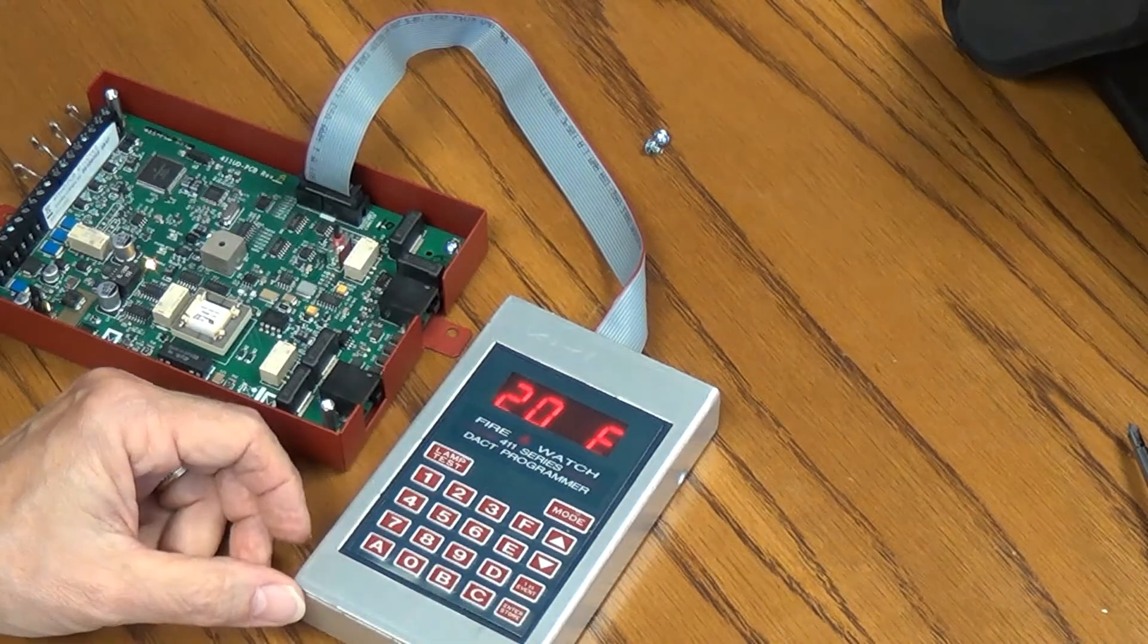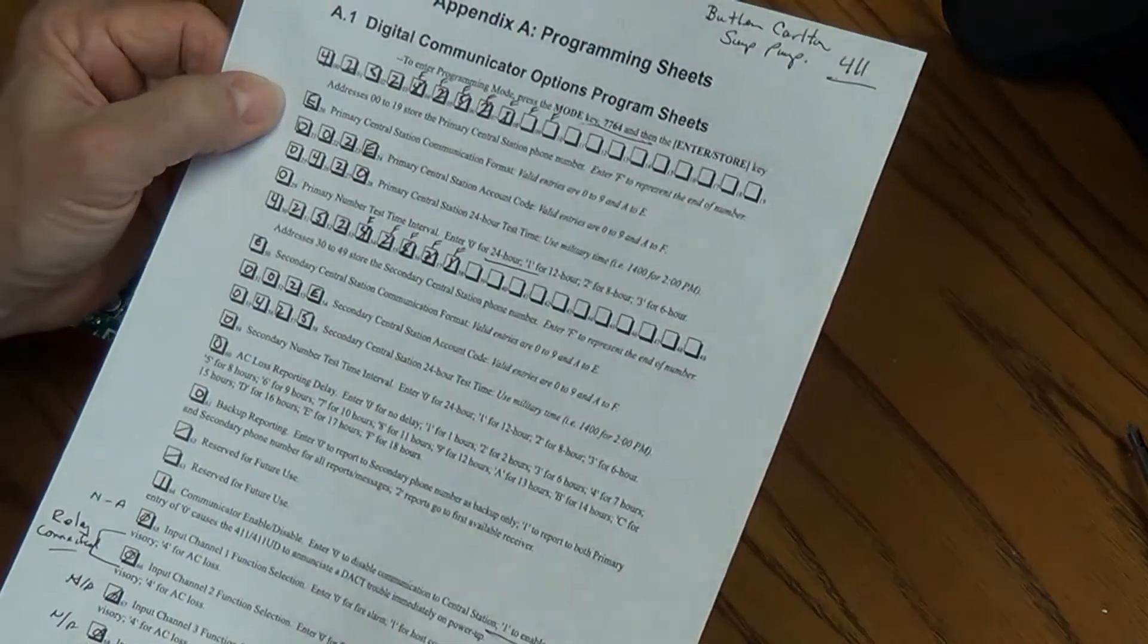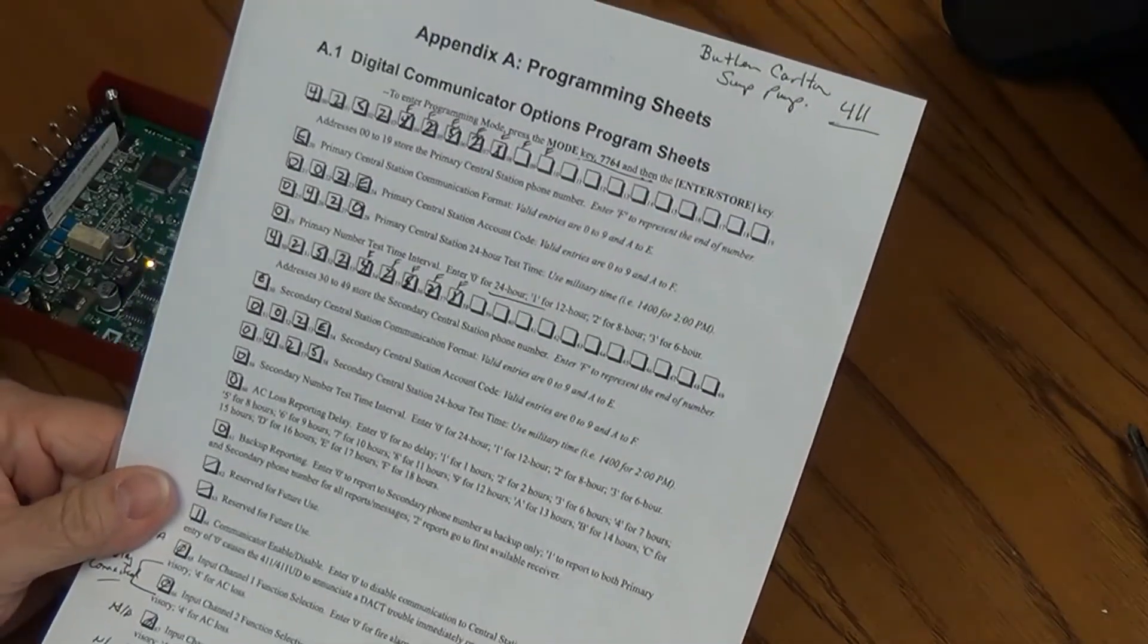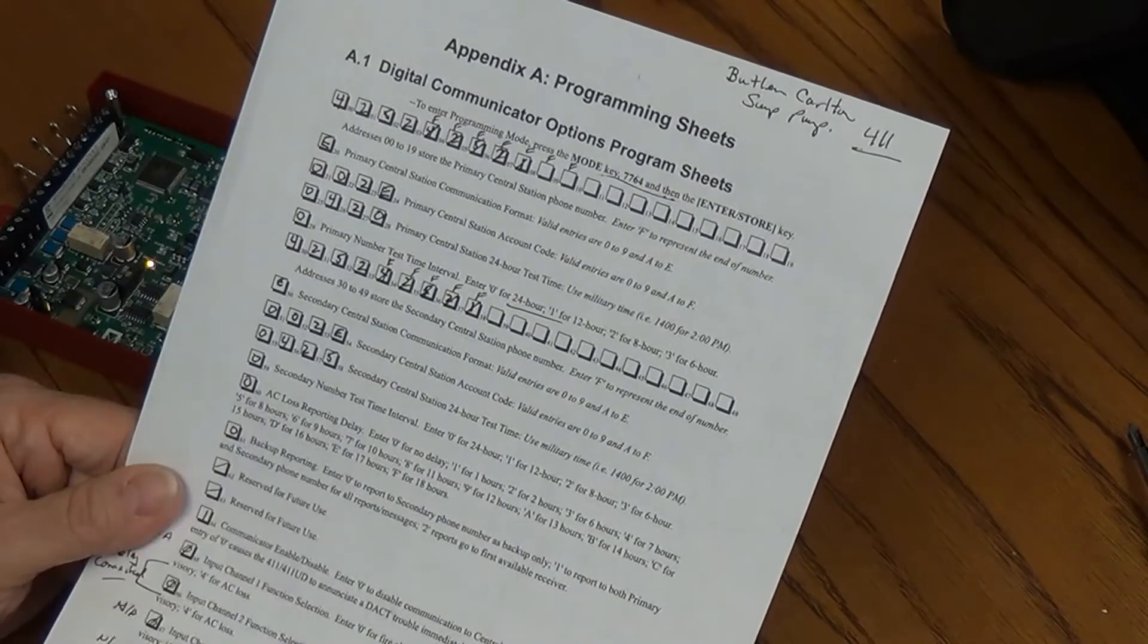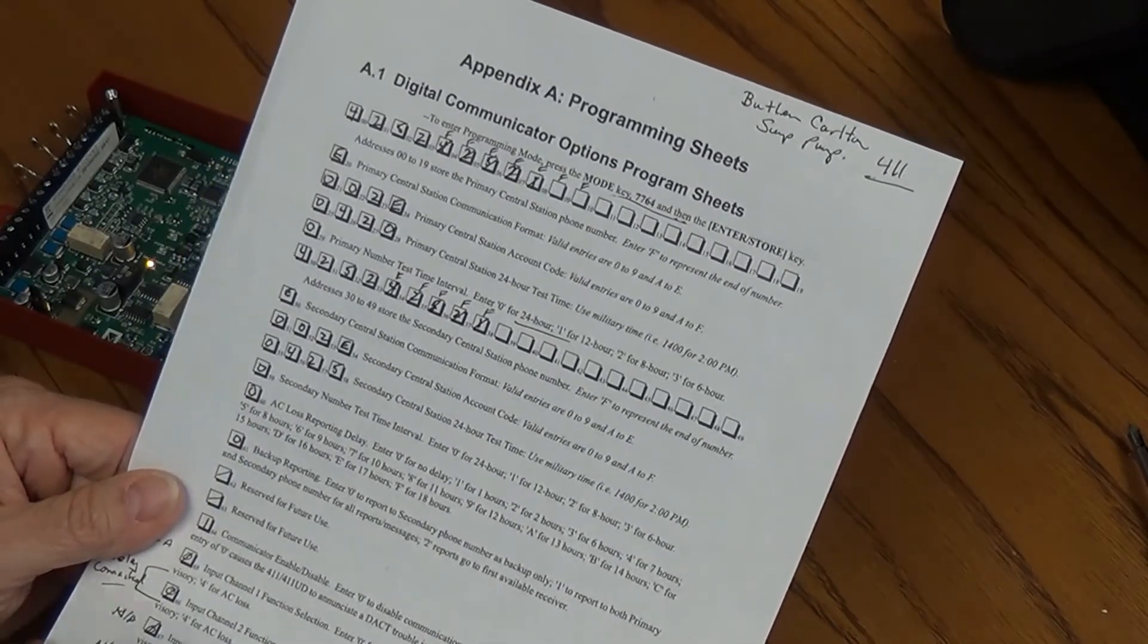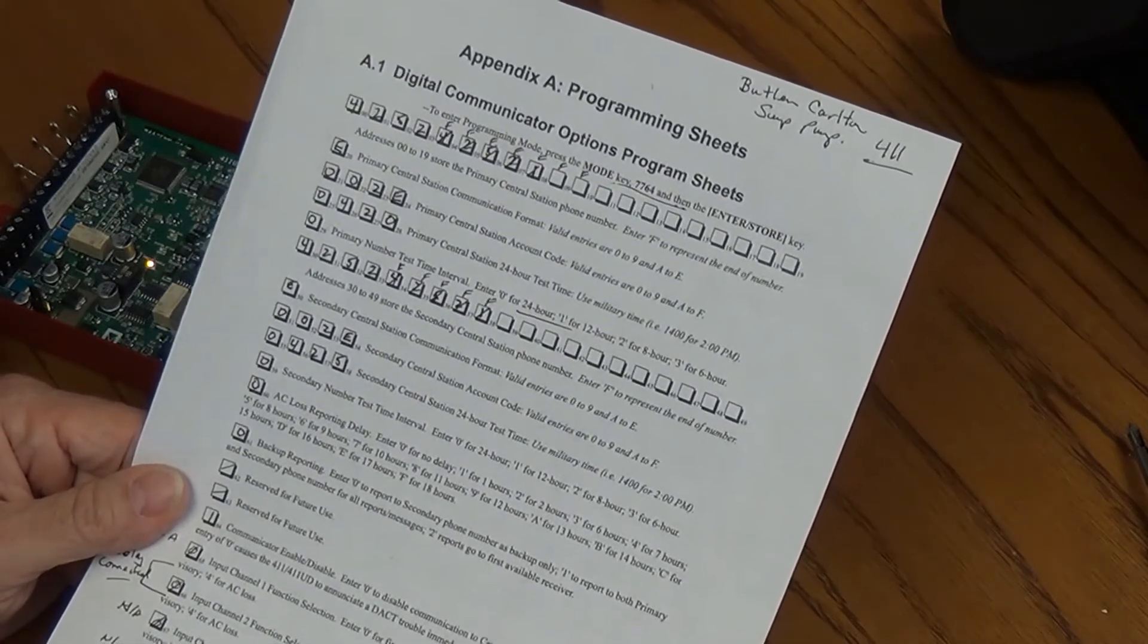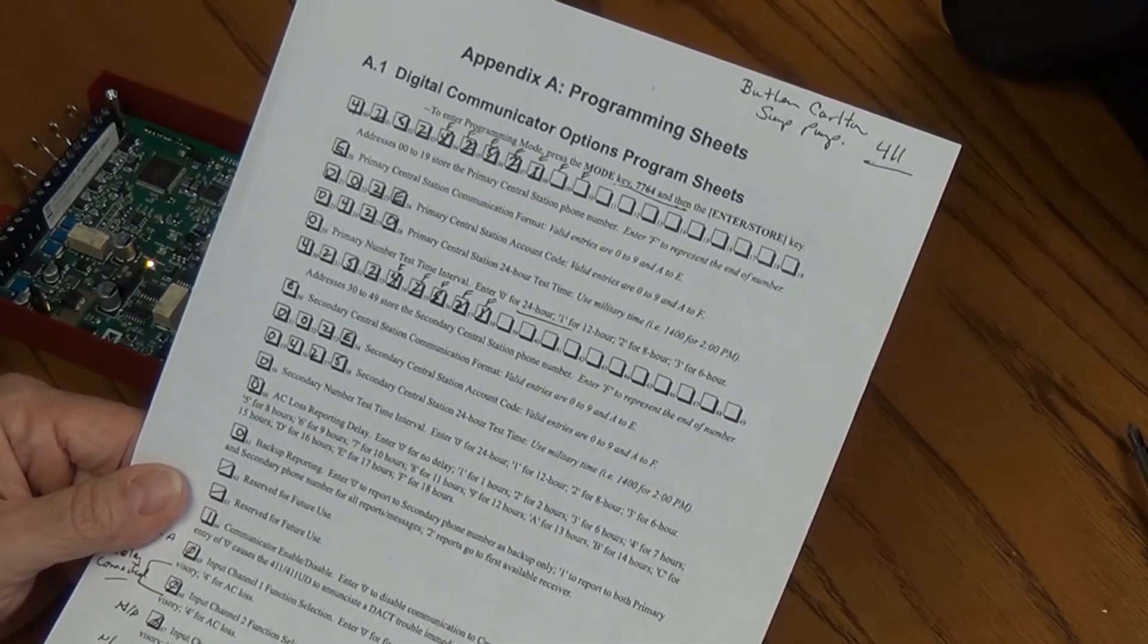Here we are in slot 20 now. Slot 20 is E, and that's what we're going to leave it as. That's the primary central station communication format. E for us is what we use, that's the Ademco alarm. And the next 4 after this is going to be our account. Let's say we're going to program this for alarm 2E. That's building 2, and that's our sump pump alarm is 2E. So we're going to enter in 002E. We're going to put those leading zeros in because we have four slots to fill.